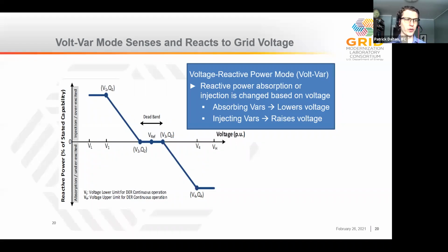This first one is the volt-VAR mode, which senses and reacts to grid voltage. On this chart, the vertical axis shows reactive power, so the injection or absorption of that reactive power component, and that's a function of the horizontal axis, which is the system voltage.